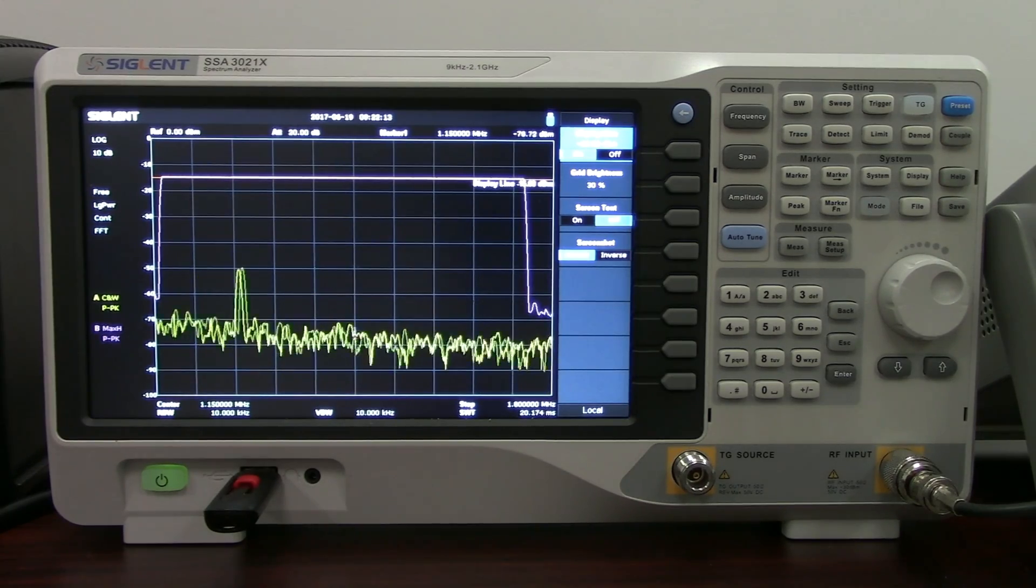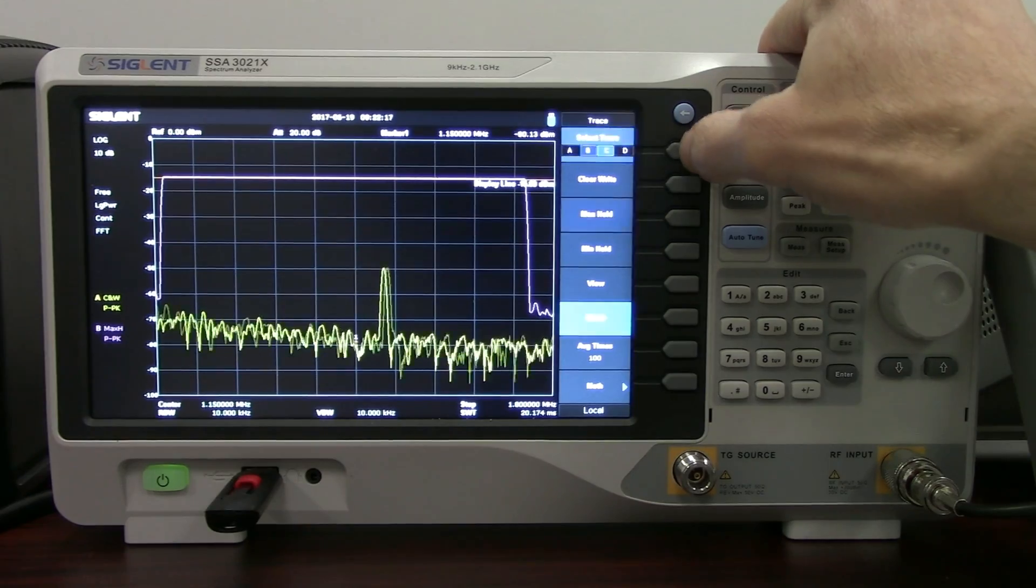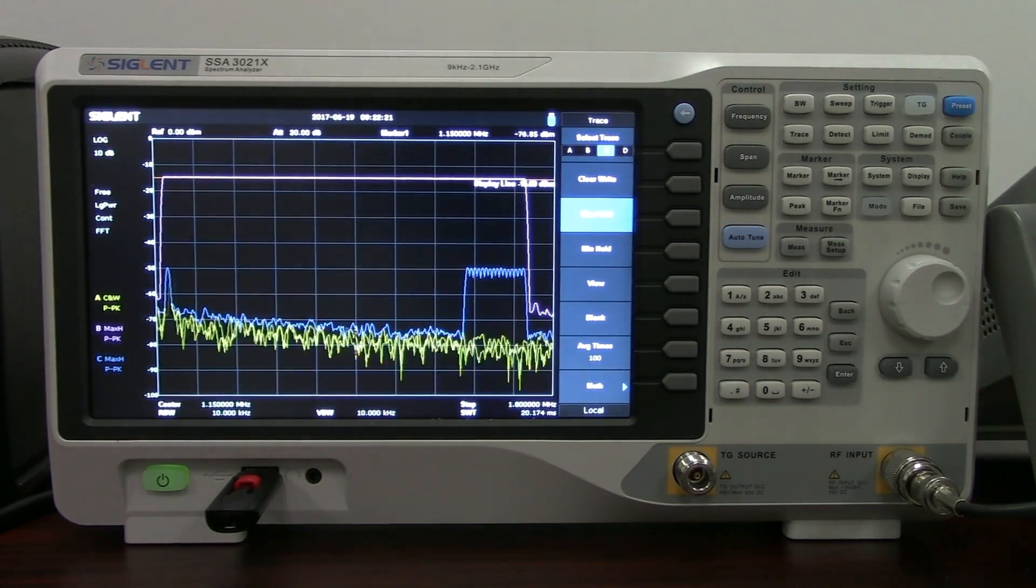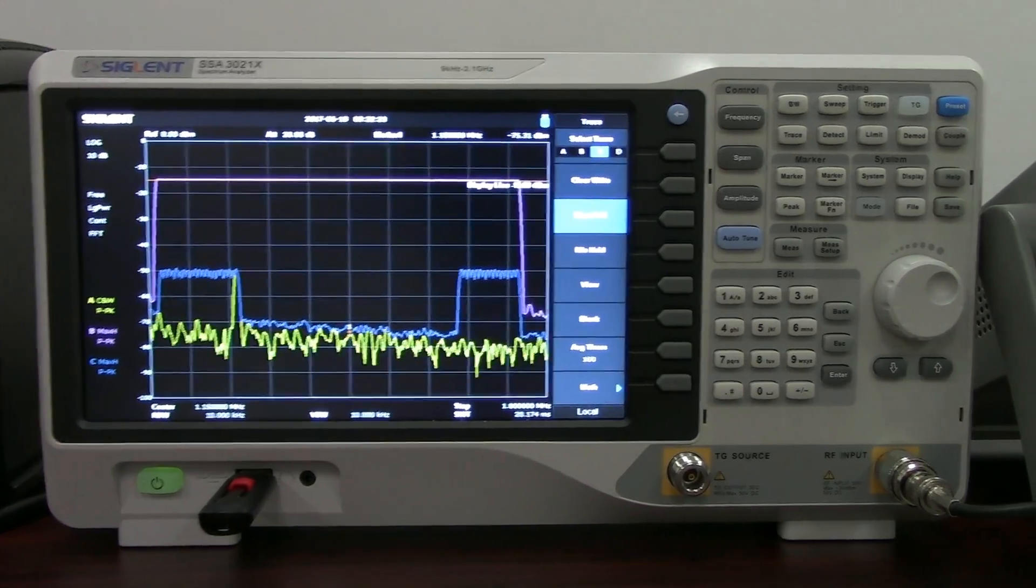And so here is our minus 15 dBm and now we'll adjust down to minus 50 and we'll enable that third trace to do a max hold as well. And now we'll trace out that minus 50 dBm sweep as before. And again here we have that minus 50 dBm and we're doing the same exact sweep.